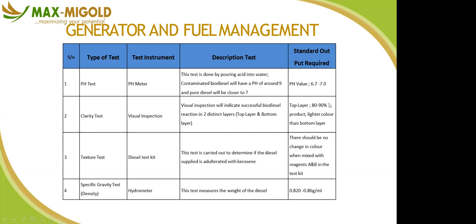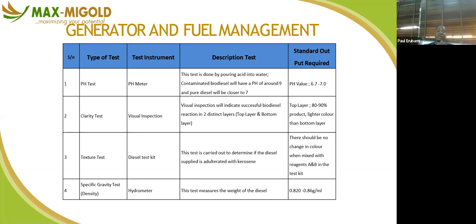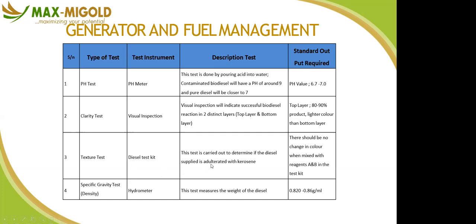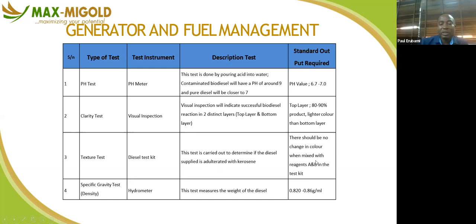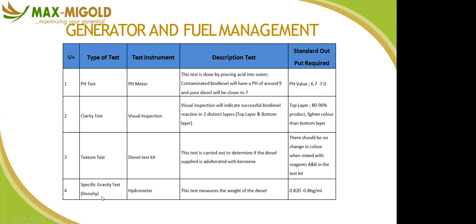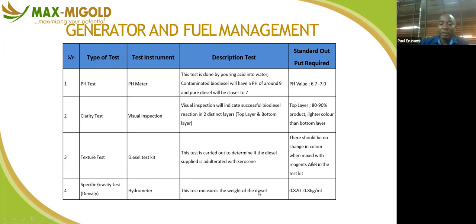If the color is not okay, we have every right to say, I'm not buying this diesel, I'm rejecting it. If you feel the color is not okay, there's another test that you need to carry out. This test is carried out to determine if the diesel supplied is adulterated with kerosene. So if there is a mix up somewhere with this test, we're able to know that the diesel is adulterated, we reject it. We have the specific gravity test, that's the density test, when you use a hydrometer.